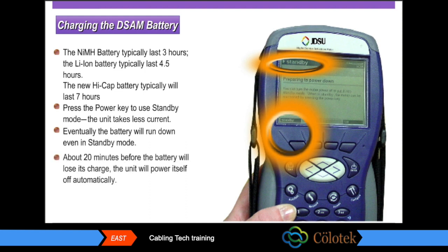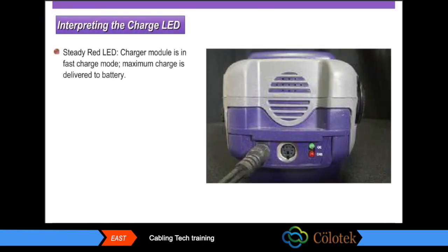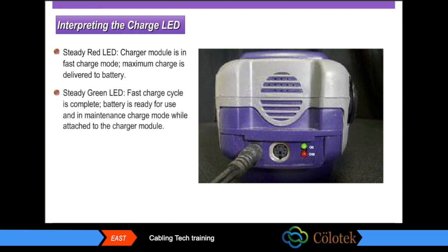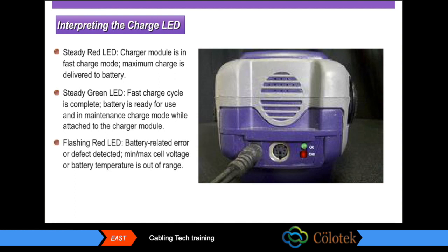About 20 minutes before the battery will lose its charge, the unit will power itself off automatically. Recharge with the plug charger or car charger. A steady red LED on the battery module means it's in fast charge mode and maximum charge is being delivered to the battery. A steady green LED means the fast charge cycle is complete and the battery is ready for use in maintenance charge mode. A flashing red LED means a battery-related error or defect is detected, or a min-max cell voltage or battery temperature is out of range.